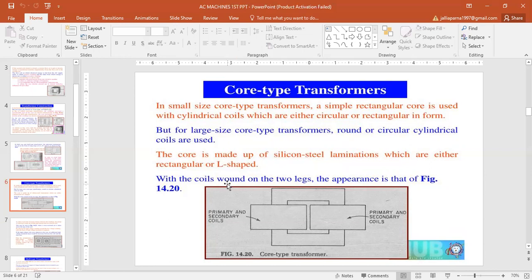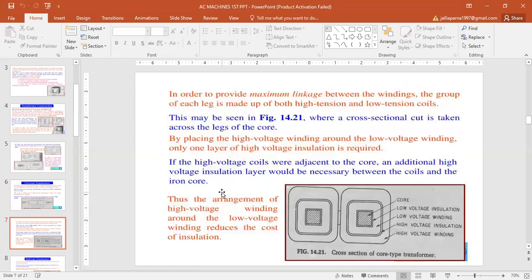With the coils wound on the two legs, the appearance is that figure. In order to provide maximum linkage between the windings, the group of each leg is made up of both high tension and low tension coils. This may be seen when a cross-sectional cut is taken across the legs of the core.